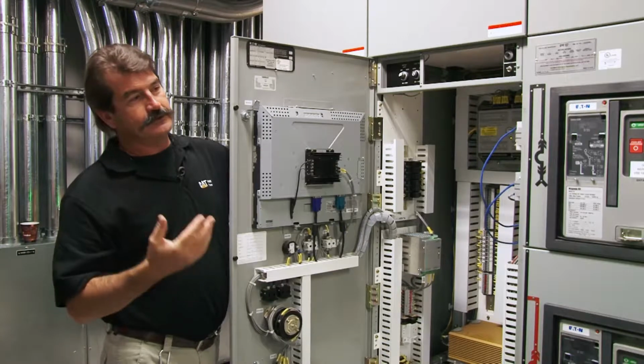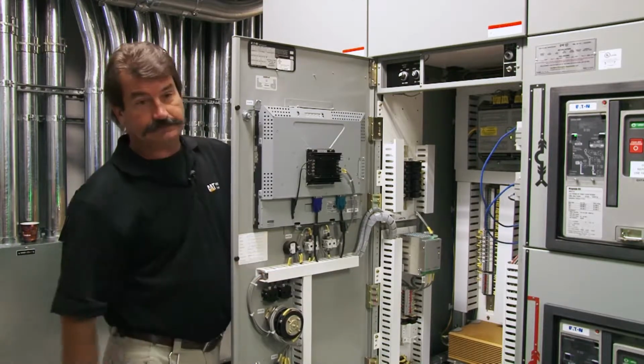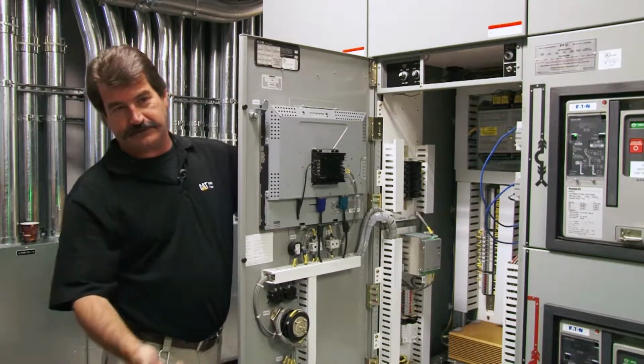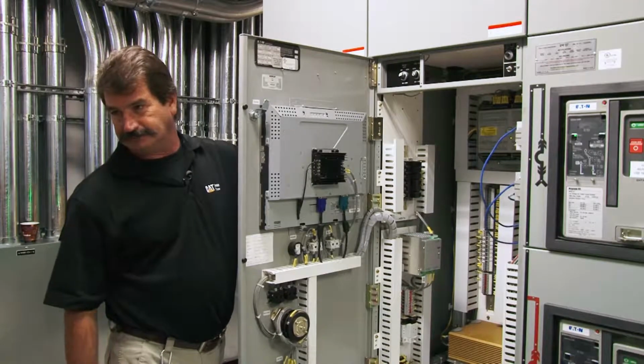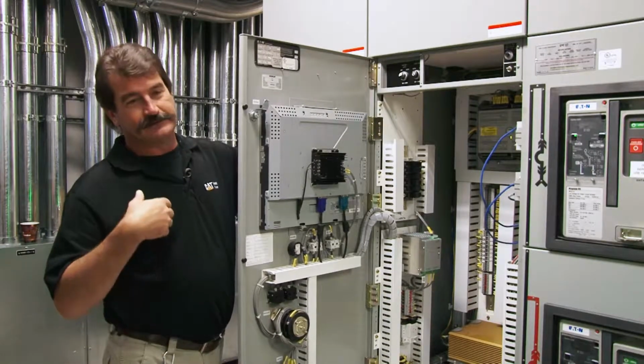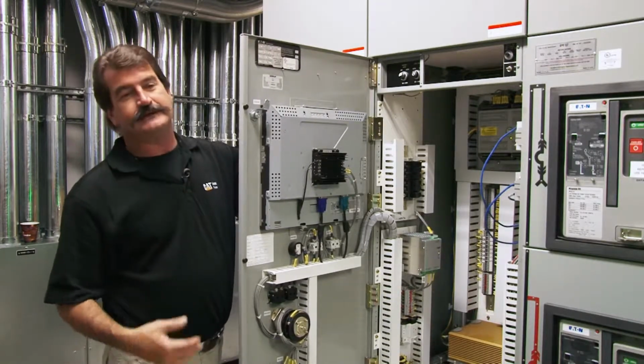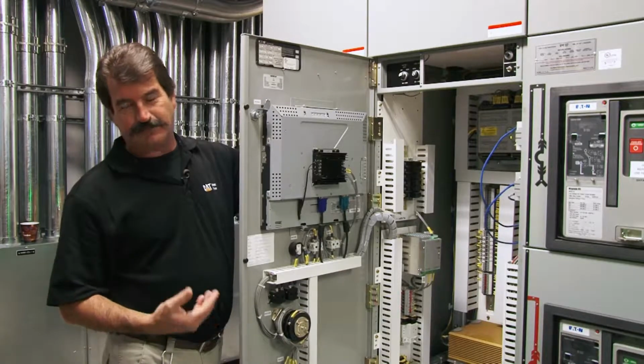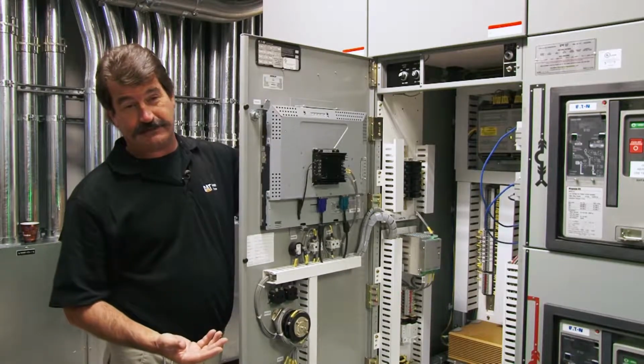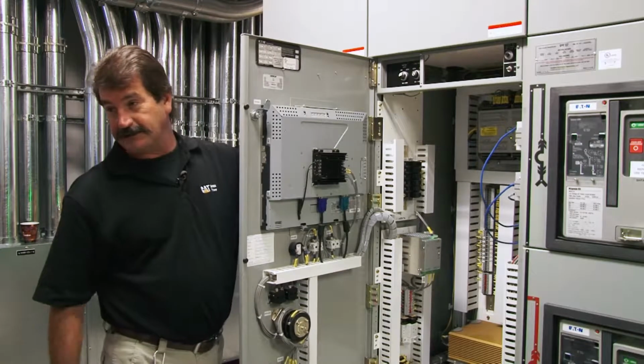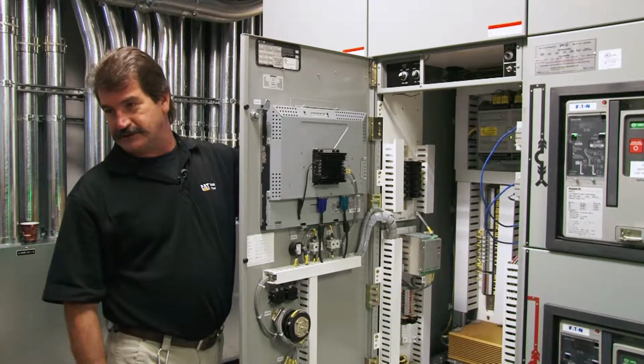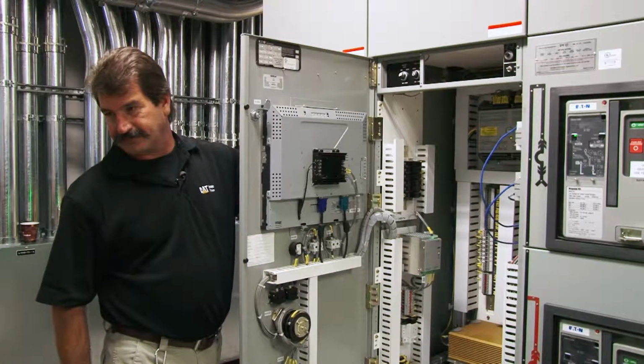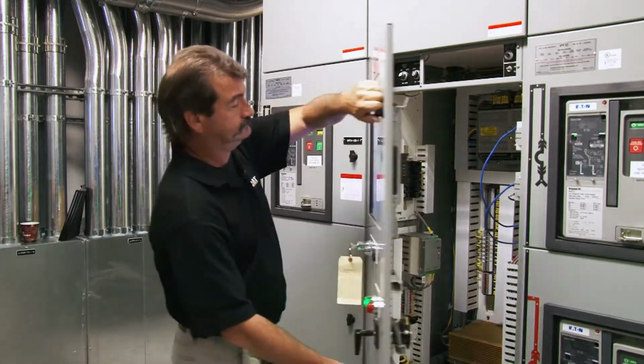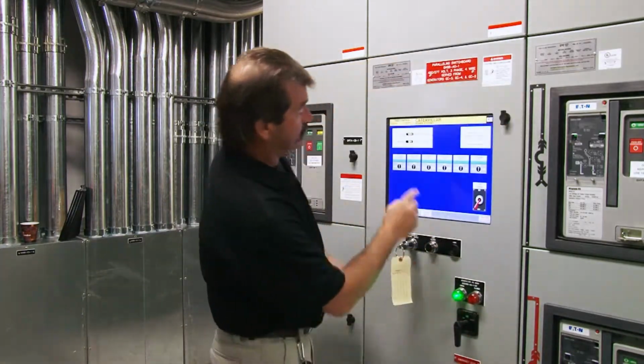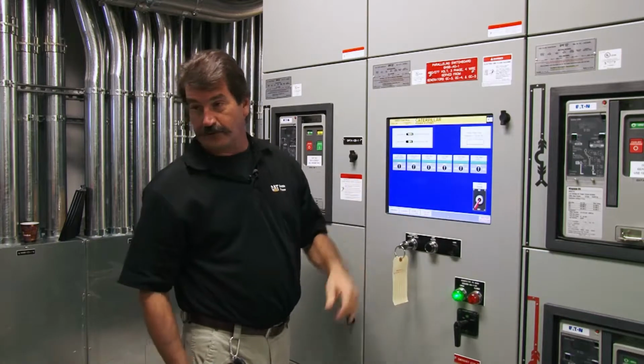Usually in other places they'll hook their ATSs into those relays. So whenever it's level 1, level 2, level 3 — if it's a smaller hospital not using distribution breakers much — they'll hook their ATSs right into there and use that to load shed their ATSs. So that's what this is for, controlling those relays.